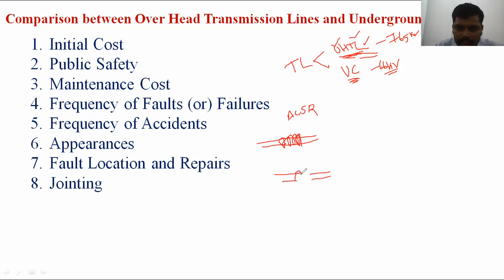Again, we use a lug and do the jointing with the help of a bolt and nut. For single core cable from 2.5 square mm or 4 square mm up to 10 square mm, it is simple. Beyond 10 square mm, the jointing is very, very difficult. In underground cable, based upon the operating voltage, 33 or 66 kV are used. Up to 33 kV, and even 132 kV, we can transfer electric energy in the underground cable, but the insulation problem appears.